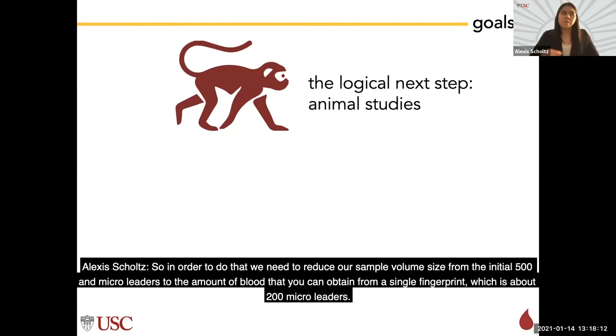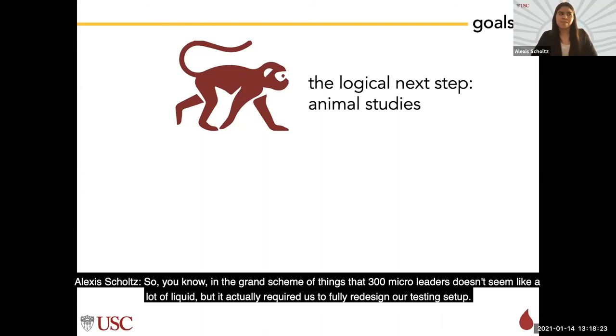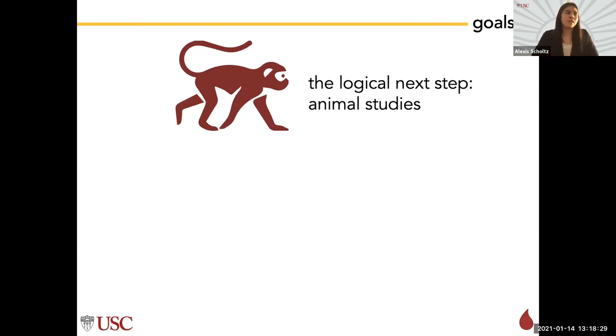So in order to do that, we need to reduce our sample volume size from the initial 500 microliters to the amount of blood you can obtain from a single finger prick, which is about 200 microliters. In the grand scheme of things, that doesn't seem like a lot of liquid, but it actually required us to fully redesign our testing setup.